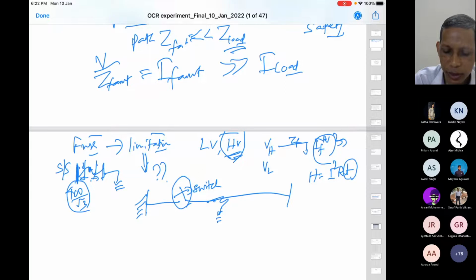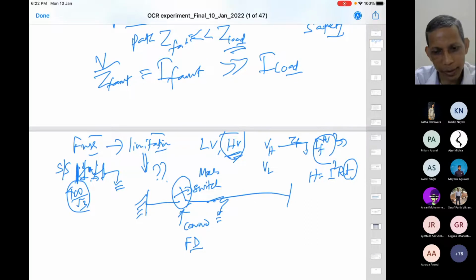To operate this mechanical switch, you need to command it, and that command comes from a fault detector. This fault detector detects a fault and classifies whether it is a fault situation or a non-fault situation. Accordingly, it commands the switch to open, or if it is a sound situation, the switch remains in contact. So this is the functionality.